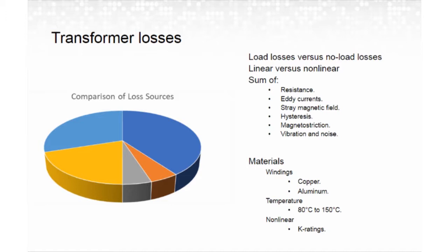Winding resistance losses, as listed here, are due to current through the winding, which results in power dissipation. Eddy currents are induced in the core and result in resistive heating. Stray magnetic field losses include energy put into generating a magnetic field, but some of that magnetic field isn't inducing a current in the secondary. You can consider this as leakage flux, and this leakage can induce eddy currents in adjacent materials. Hysteresis losses occur from magnetic fields changing direction within the core. Magnetostriction vibration is another form of lost energy, and really both eddy currents and magnetostriction are responsible for the humming or the buzzing associated with transformers. Both noise and vibration are examples of work being done, and that work is part of system losses.